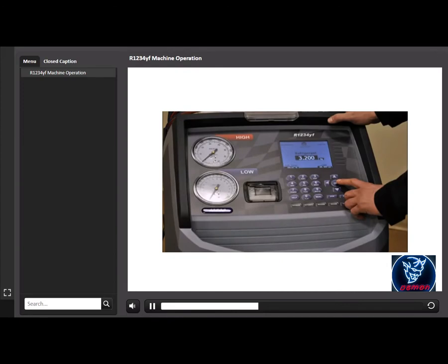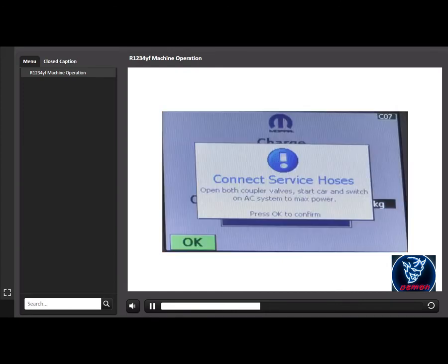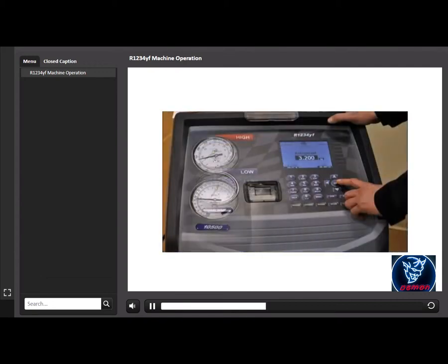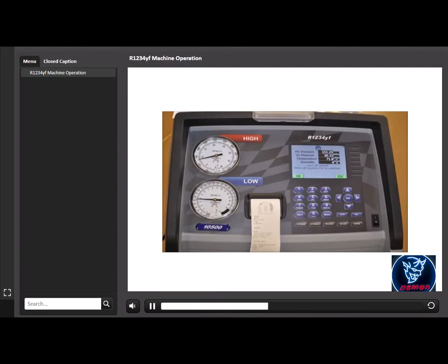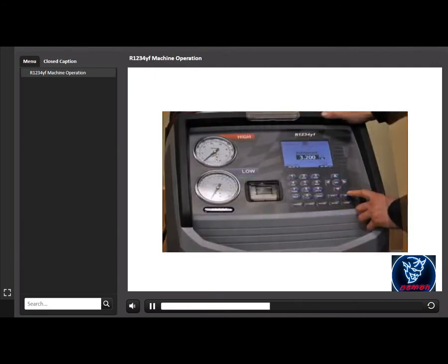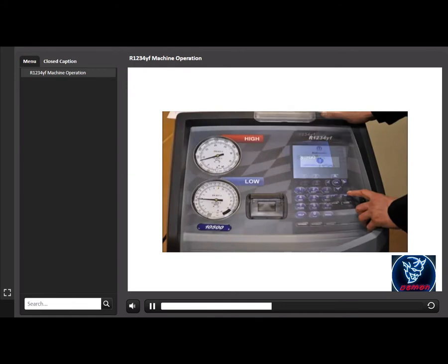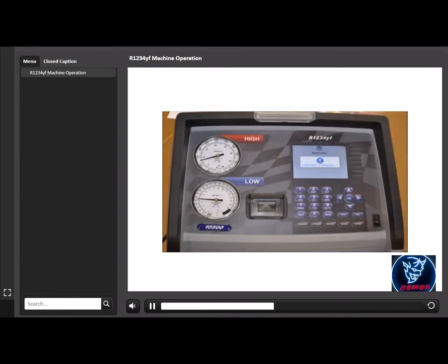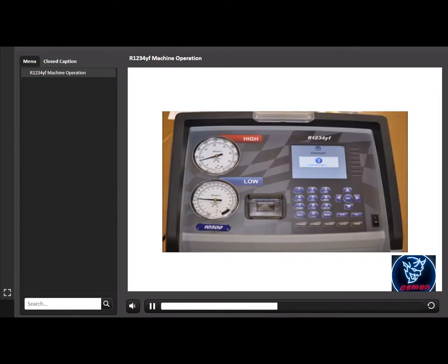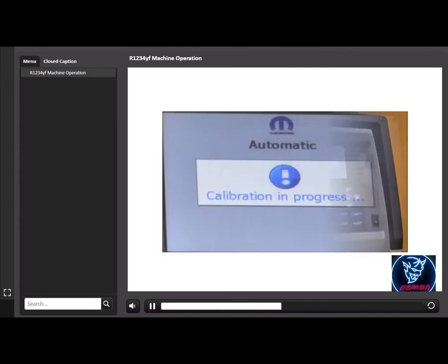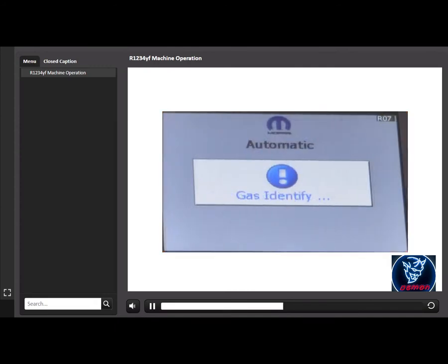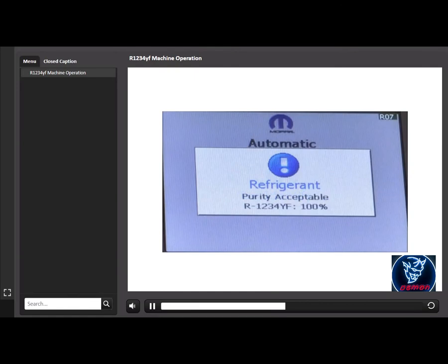If OK was selected, follow the prompts to start the vehicle and set the AC system according to Service Manual AC Performance Test requirements. Press OK after the pressure stabilizes. Press OK again to print the data. Then press Escape to continue with the recovery sequence. The machine checks the refrigerant in the vehicle to verify it is R1234yf and not contaminated, which is required by SAE J2843. The machine will display the following screens: calibration in progress, gas identify, and refrigerant purity acceptable.